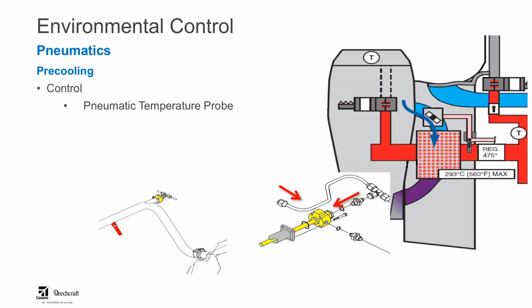And as that probe senses about 475 degrees Fahrenheit, the head cracks open and allows service air pressure to move on downstream to the modulating valve and open it. Then we use that modulating valve to rotate open and allow more cooling air through.